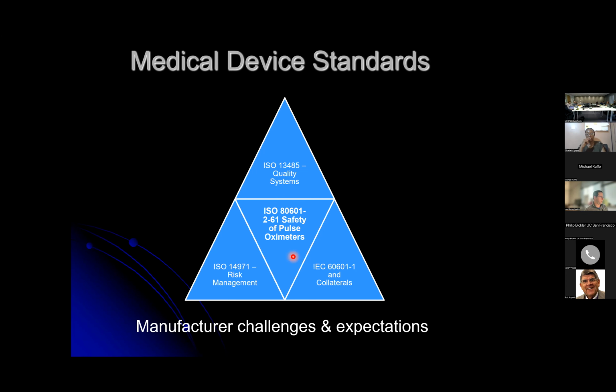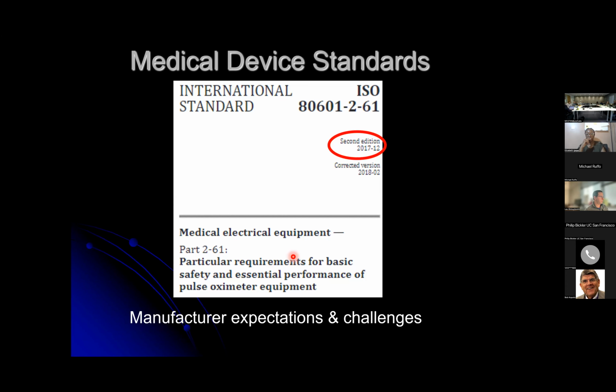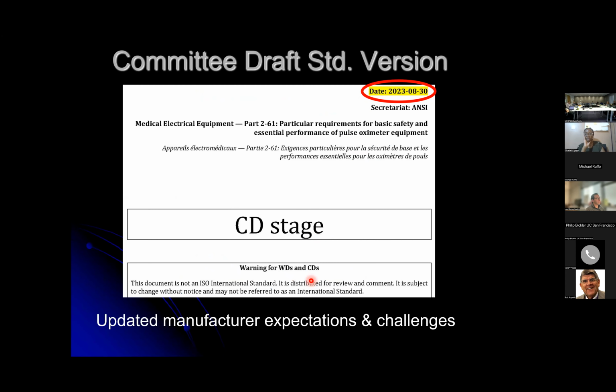manufacturer-based standards. These are the standards that a device manufacturer must adhere to in order to release their product. The last such standard was in 2017, and there was a minor update to that just a couple of months thereafter. And as you know, it's not only basic safety, what is intended by essential performance is also accuracy performance. And so that's what I will be focused upon here, because with that accuracy performance comes enhancements to the standard that I just pointed out that is now going back to 2017.